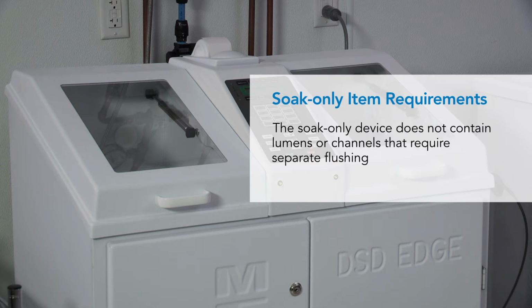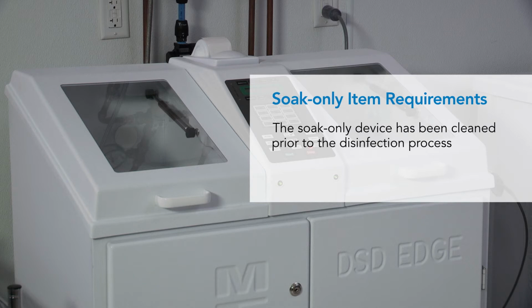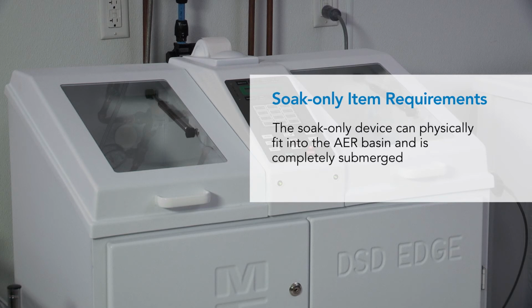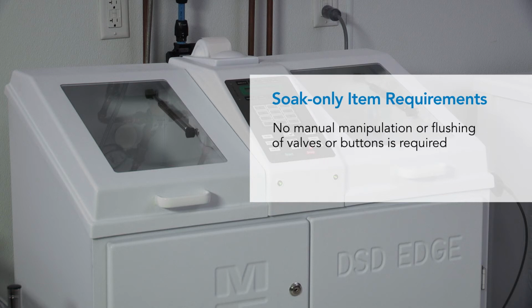The soak-only device does not contain lumens or channels that require separate flushing. The soak-only device has been cleaned prior to the disinfection process. The soak-only device can physically fit into the AER basin and is completely submerged. High-level disinfection is the standard of decontamination accepted by the facility for the devices being reprocessed. No manual manipulation or flushing of valves or buttons is required.